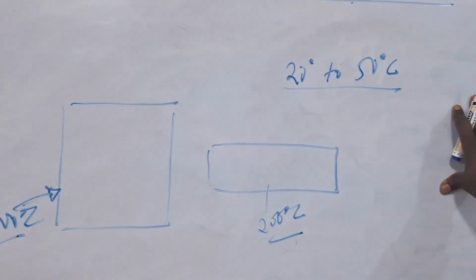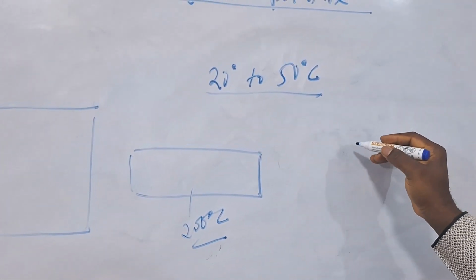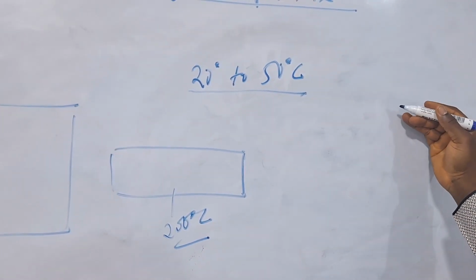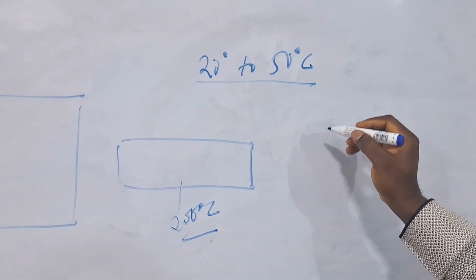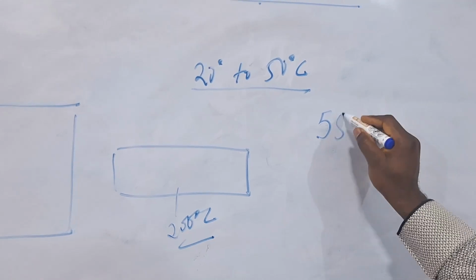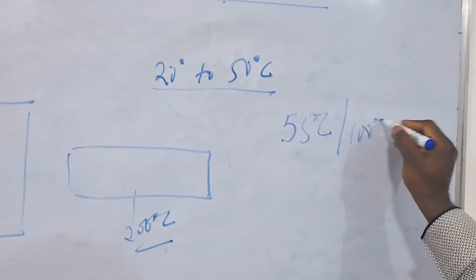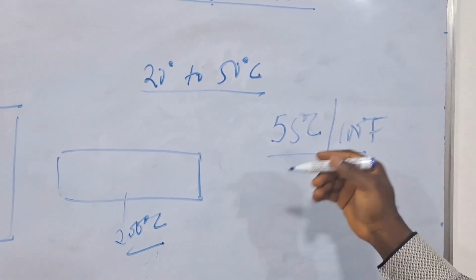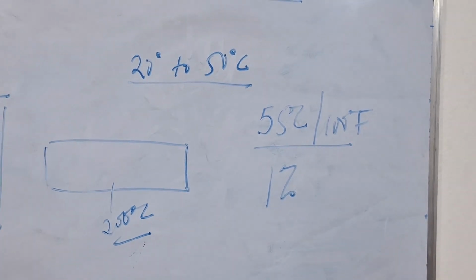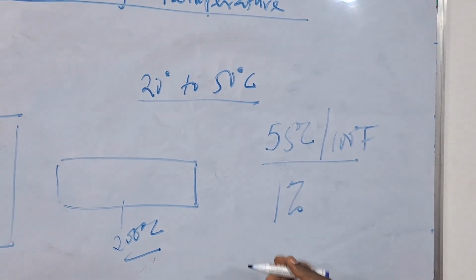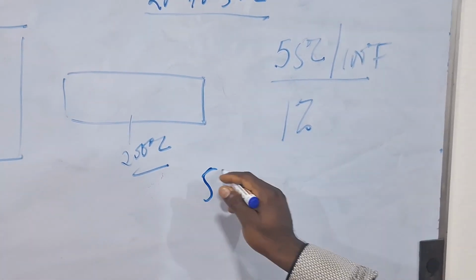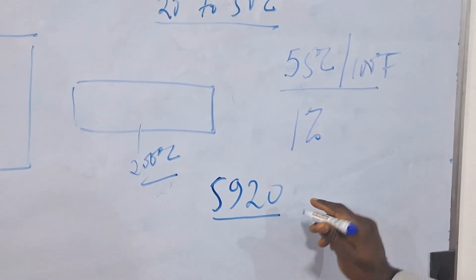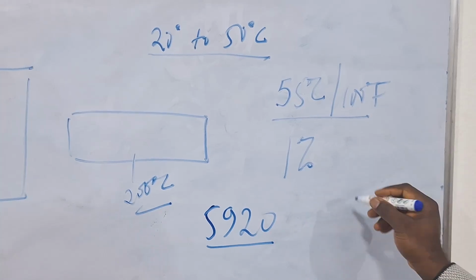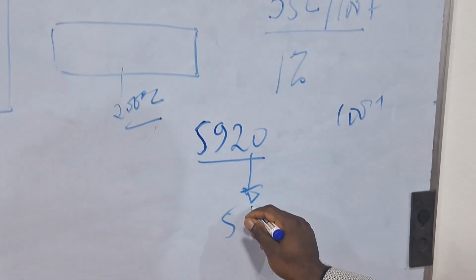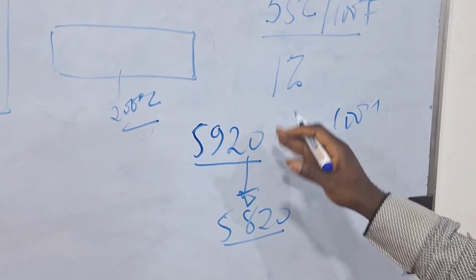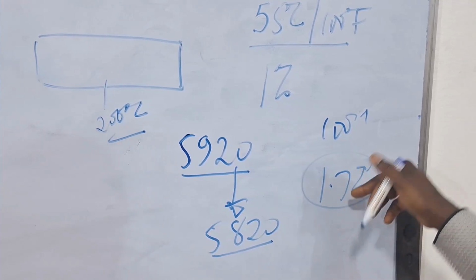In principle, the velocity of the sound wave in a material will reduce as the temperature is increasing. As a matter of fact, for every 55 degrees Celsius, which is 100 Fahrenheit of temperature change, the velocity will reduce by 1%. What this means is that if I have my normal velocity of sound at 5920, by the time I increase the temperature by 100 degrees centigrade, the velocity would have reduced to 5820. And by the time you take your thickness measurement, you will have about 1.7% difference in the thickness.